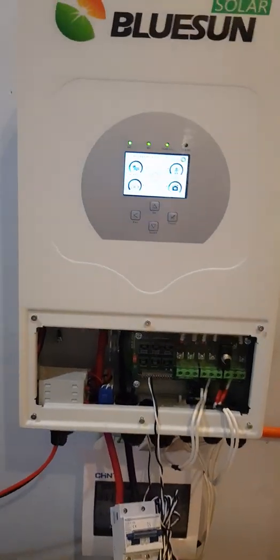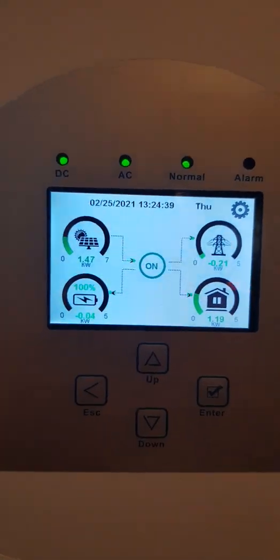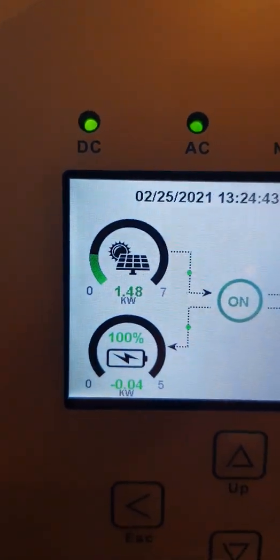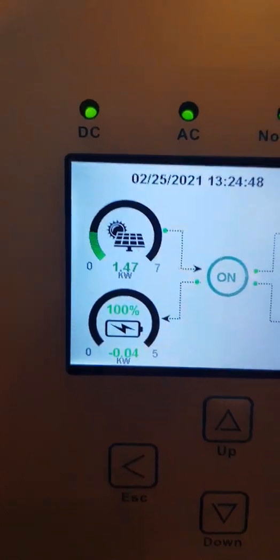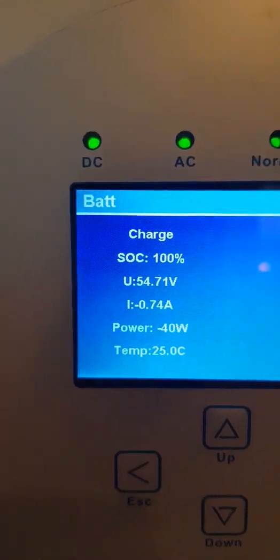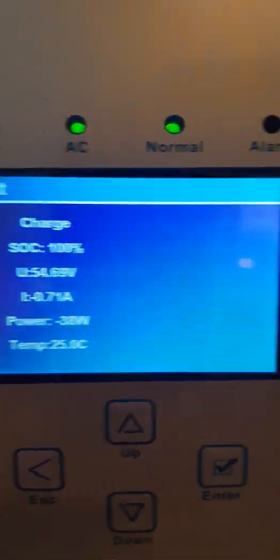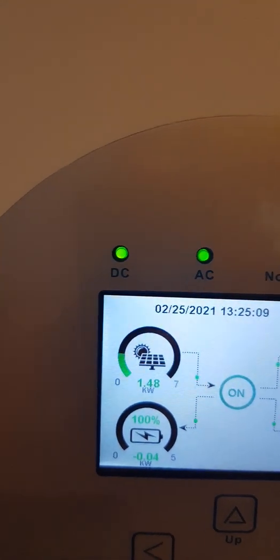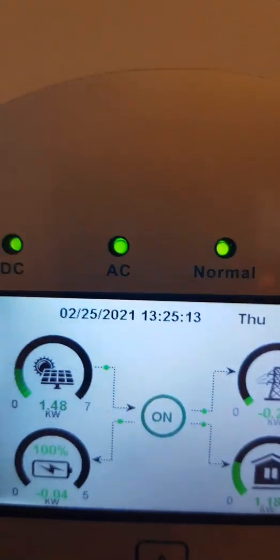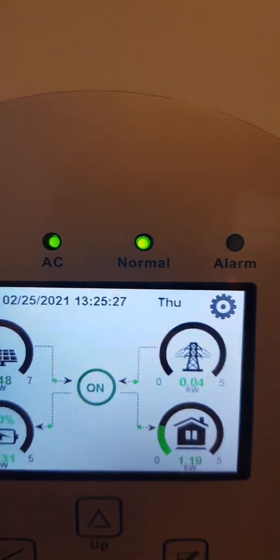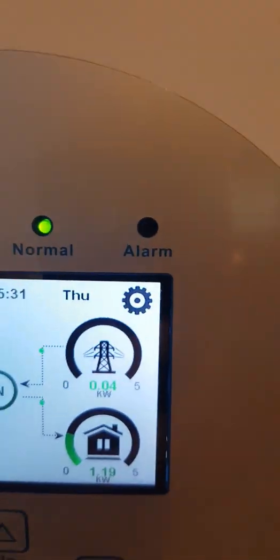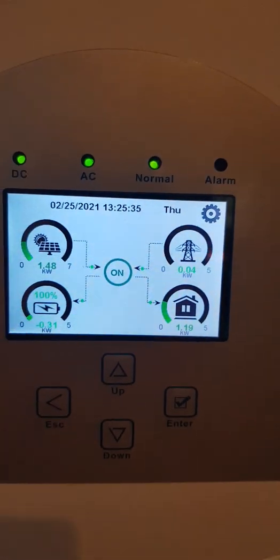So right now I will show you the setup. Currently I'm using, right now the solar panel is producing 1.48 kilowatt, and since the battery is full charge, the power it consumes charge is only for battery maintenance. Press escape. You can see the DC. When it's lit up, it means that there is solar power being produced. When the AC is lit up, it means that there is AC power from the grid. If this is normal, it means that there is no problem and the inverter is currently working in good condition. And also, if there is no alarm, it shows that the inverter is working very good.